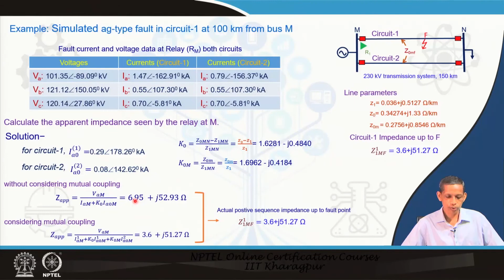So, that means the relations which you have derived are in agreement with the actual positive sequence impedance, and if you use these relations with the currents from the second line, then we will get more accurate apparent impedance. So, there will be no issue of underreach or overreach, whereas if we neglect that part, then in this case we observe that this will underreach. But again, if the phasor position of the corresponding current deviates significantly, then we may also find the overreach issue.